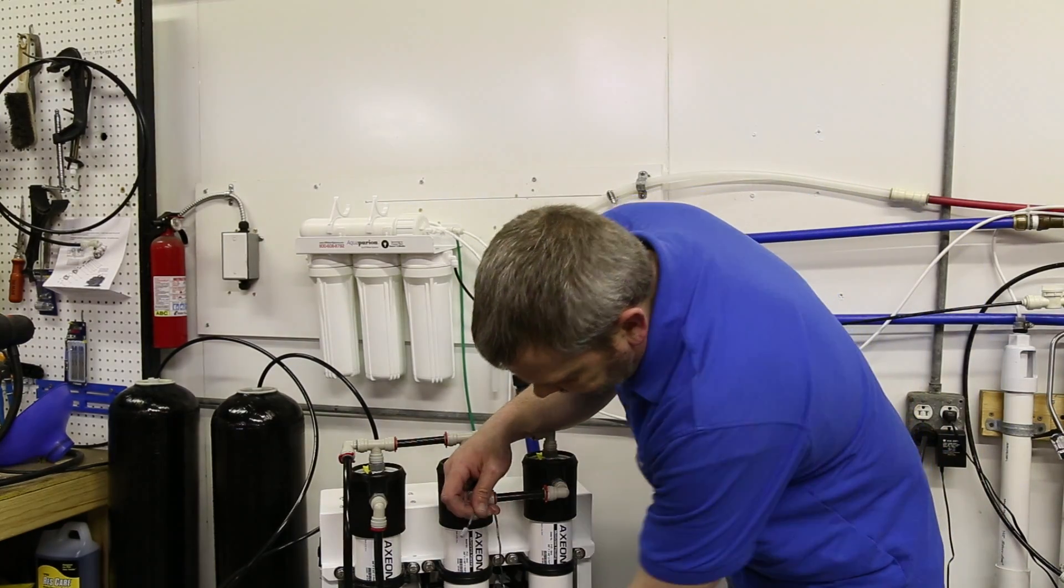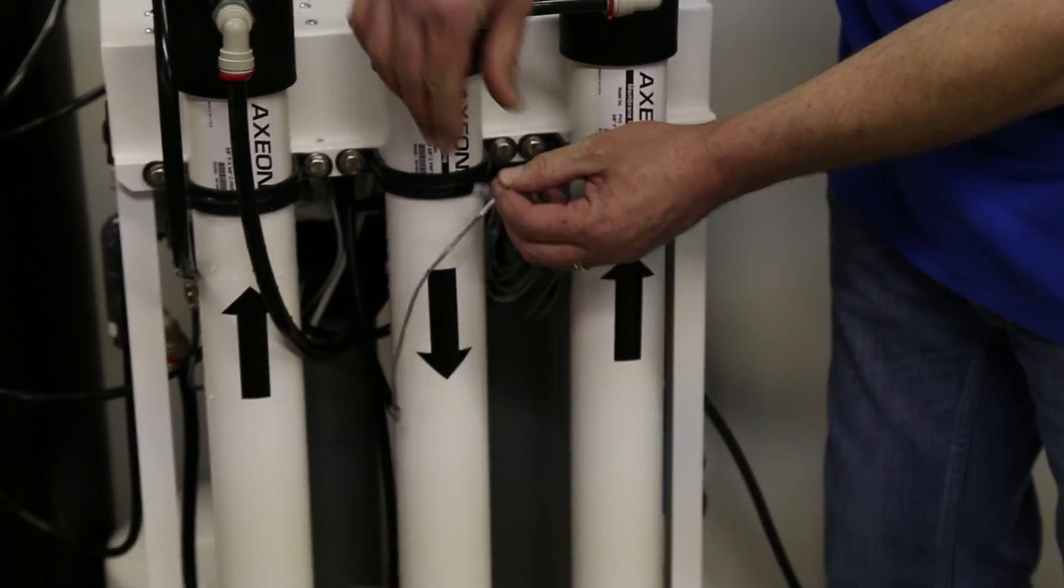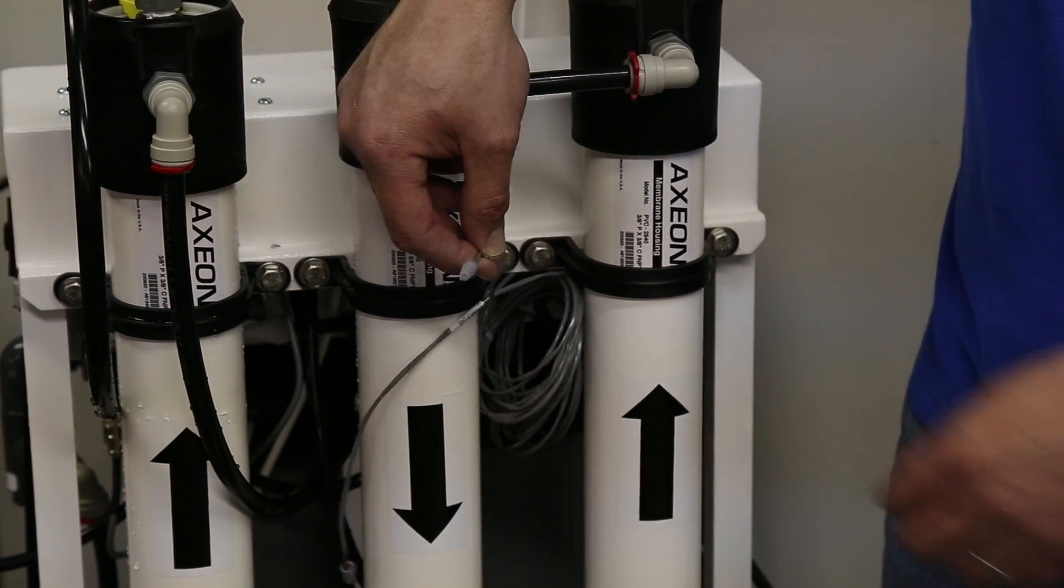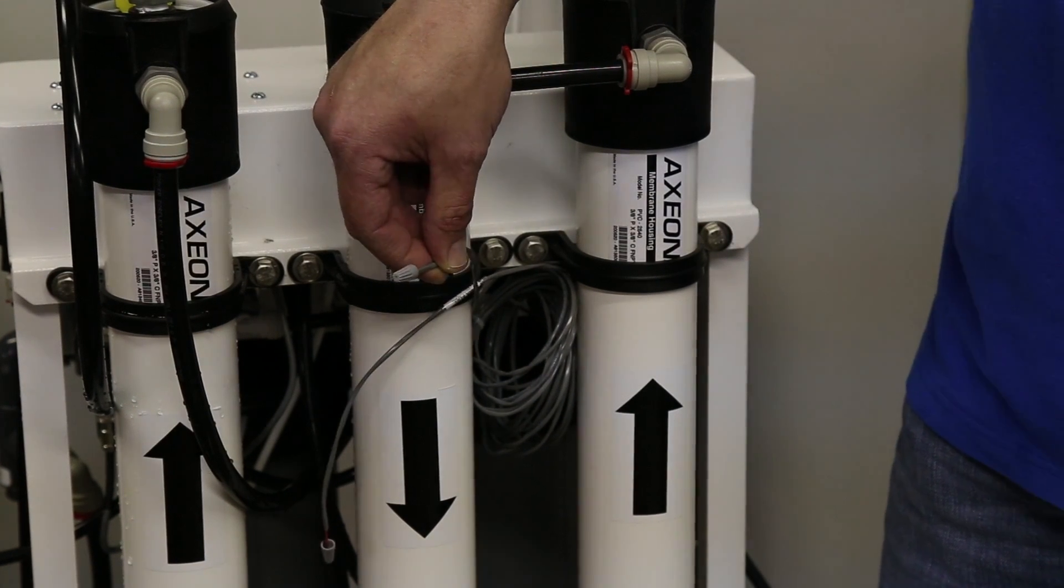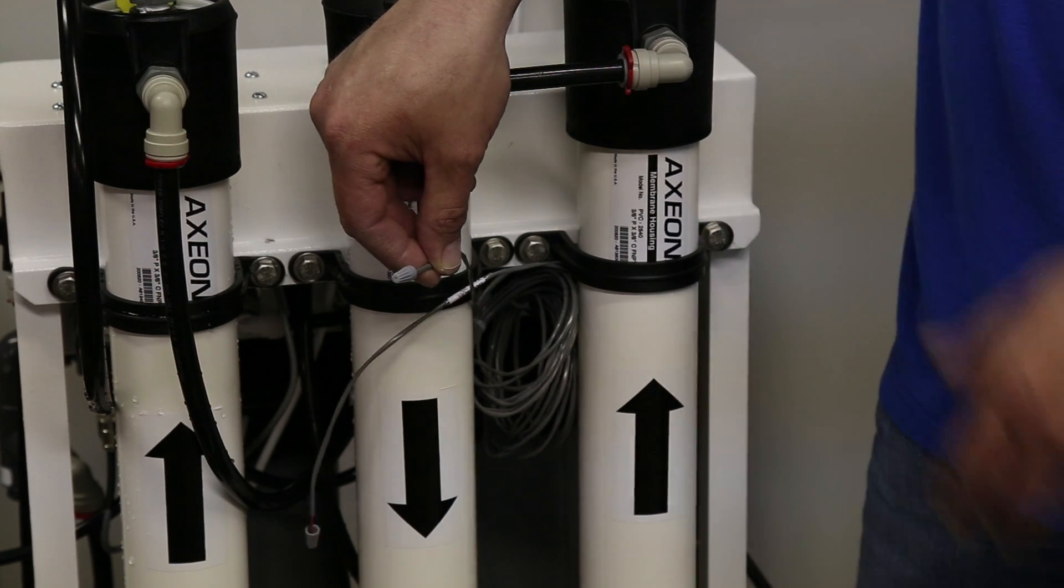Now the other one we have here is called pre-treatment lockout and it works the same way. It's still a switch closure, no voltage, and it still has to be closed for the RO to run. Now what this is for is you can actually run a circuit with an ancillary switch on some of your pre-treatment items.